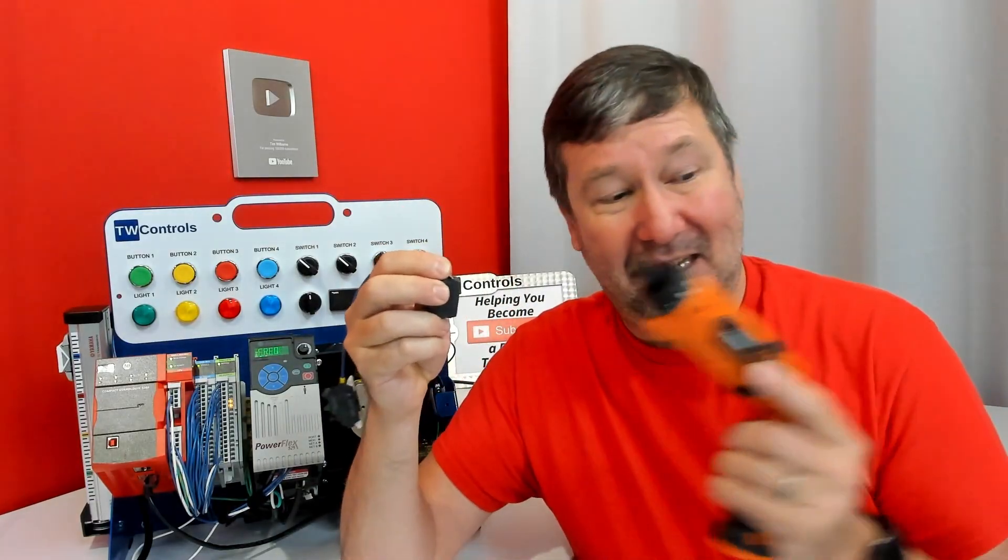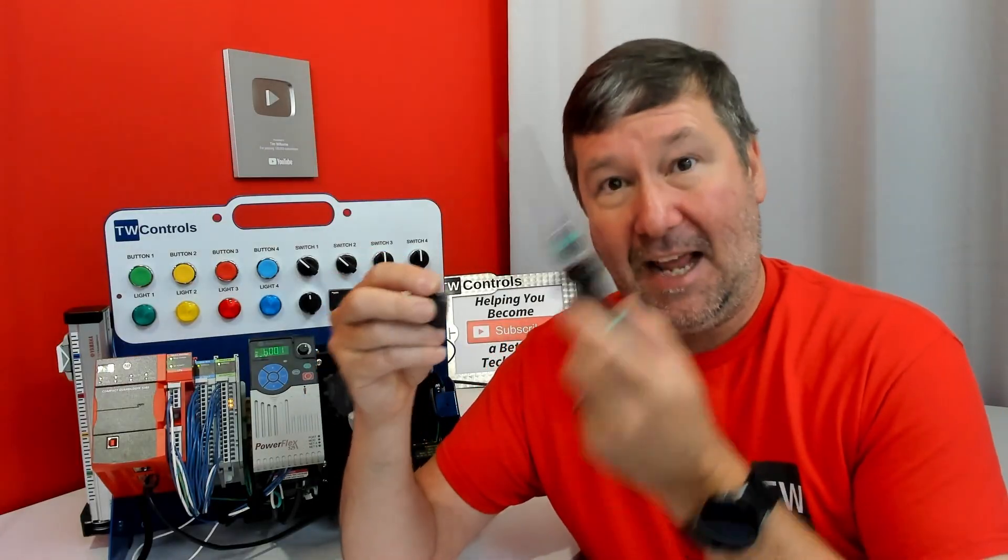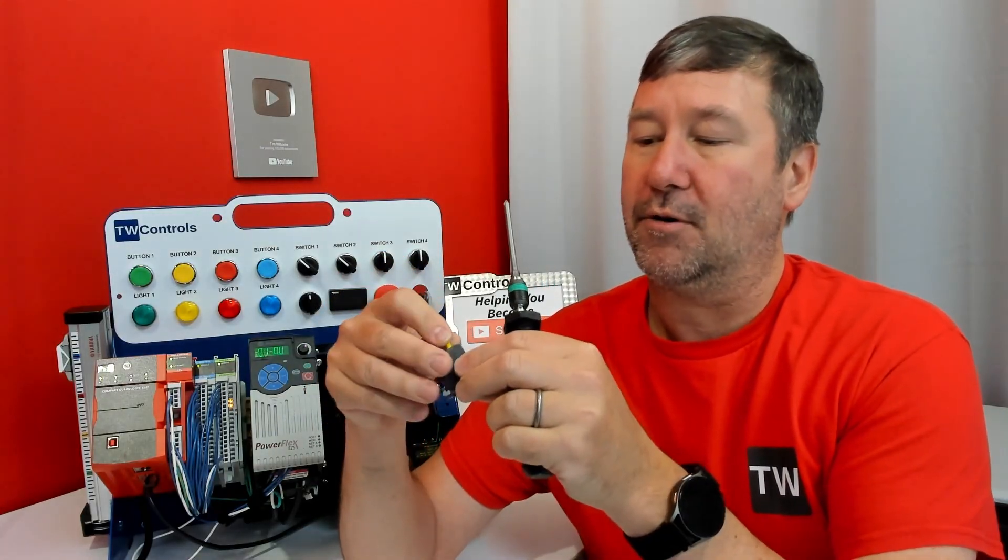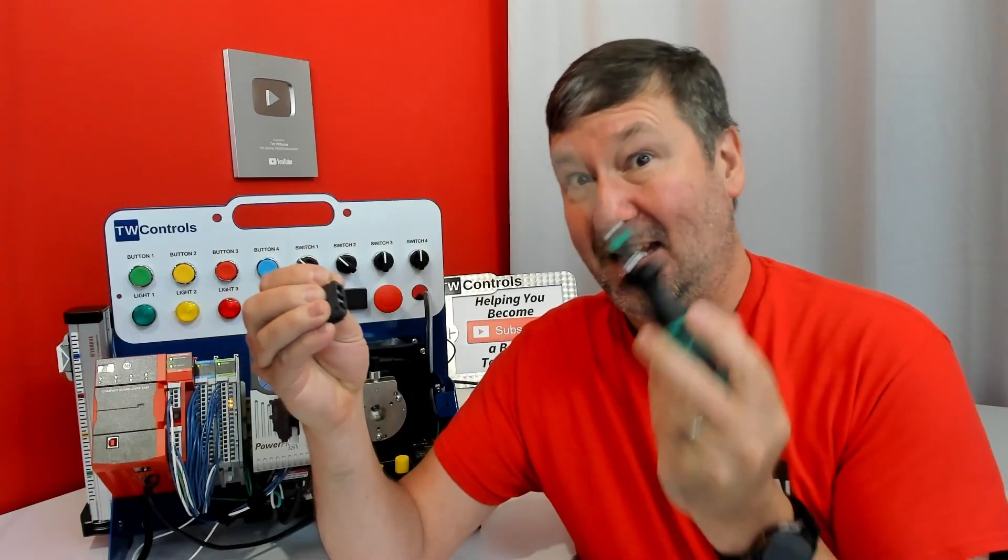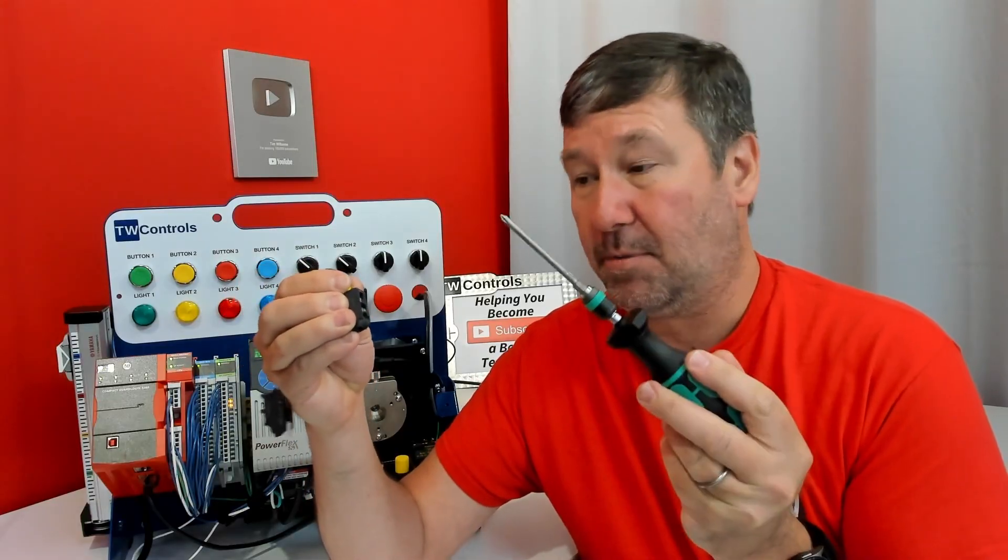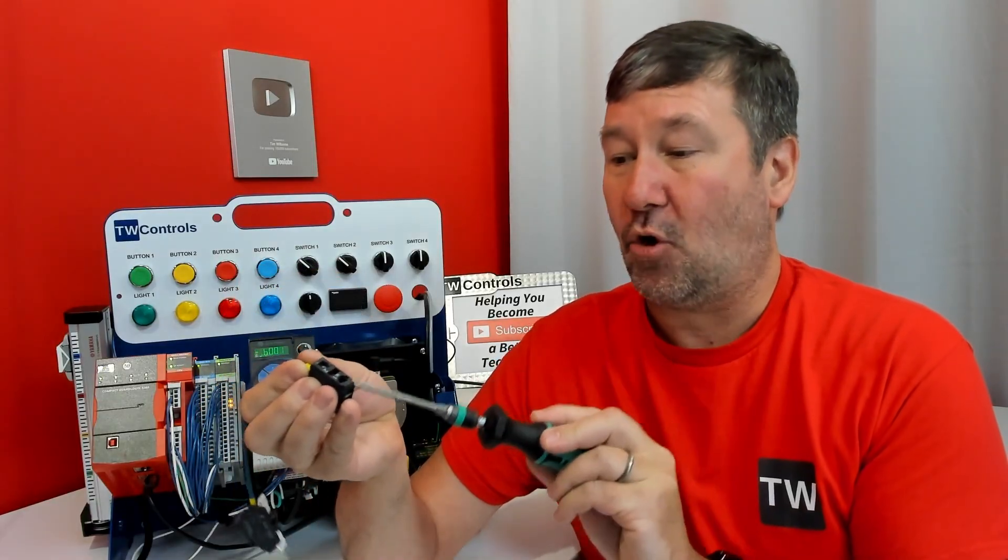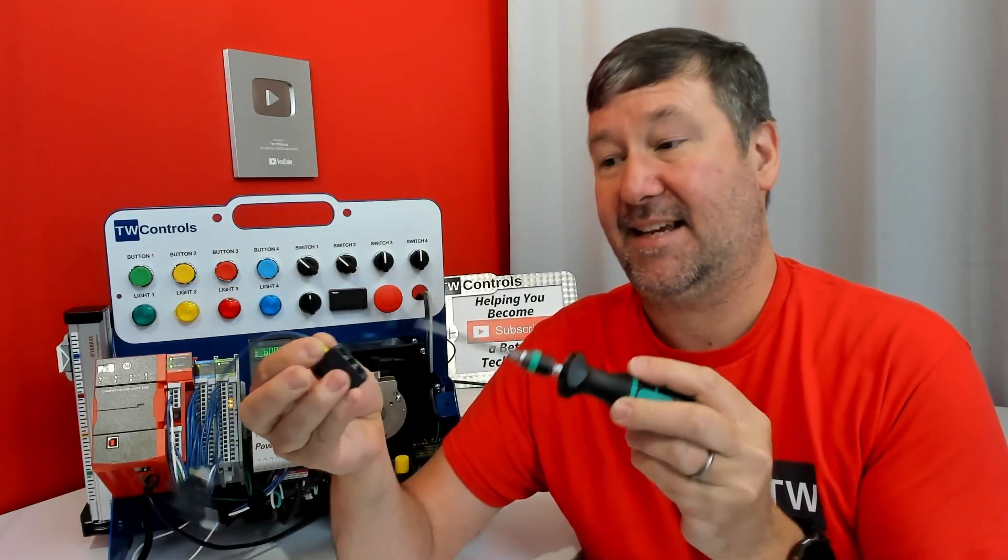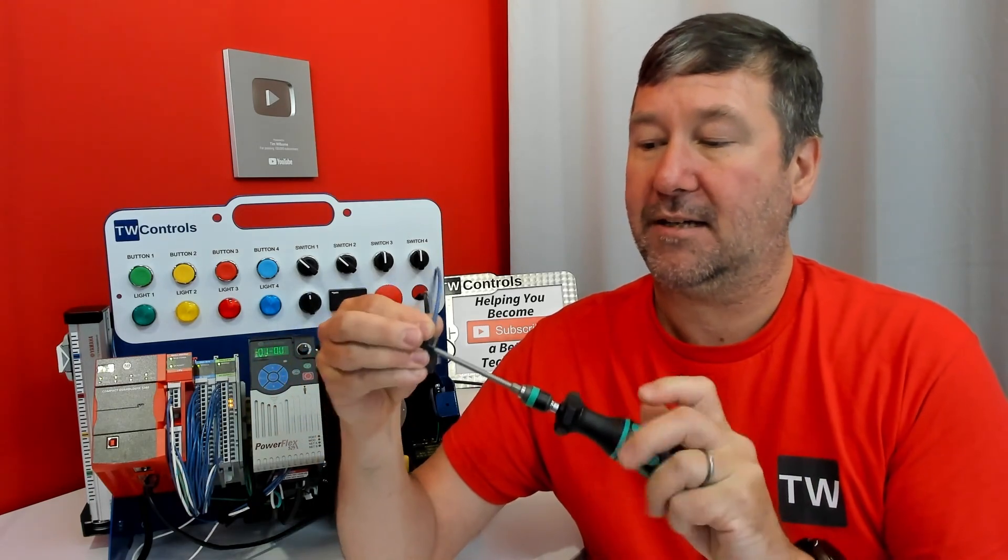You can use these to get close, but what UL requires is that we have an actual torque screwdriver and that it is properly calibrated. Then we torque it to the setting that it says on the contact block, and we can call that terminal good.